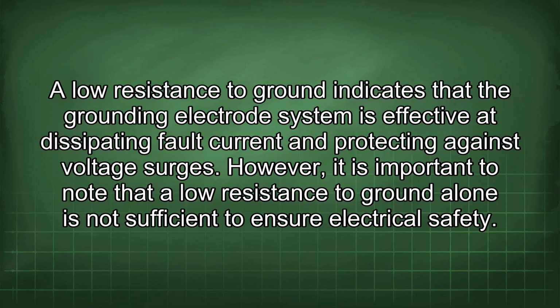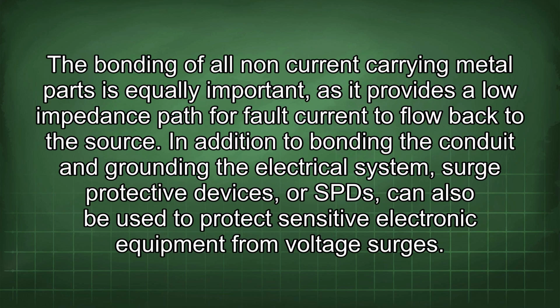A low resistance to ground indicates that the grounding electrode system is effective at dissipating fault current and protecting against voltage surges. However, it is important to note that a low resistance to ground alone is not sufficient to ensure electrical safety. The bonding of all non-current carrying metal parts is equally important, as it provides a low impedance path for fault current to flow back to the source.